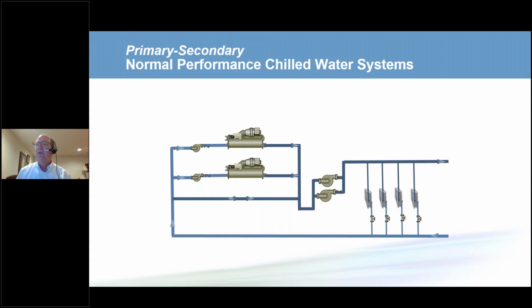Well, if we have constant flow through the chillers, but variable flow through the system, we need to have a way to make up the difference between that flow, and that's a bypass line, sometimes called a decoupler, since it decouples or separates the working pressures of the chiller pumps and the secondary pumps. This bypass line should not have obstructions in it. We don't need to control the flow rate. The water knows where to go by the operating pressures in the system.